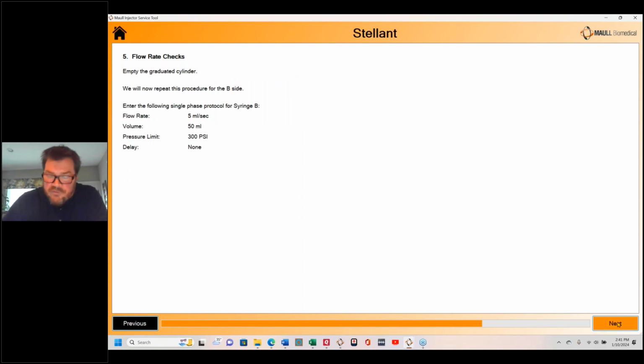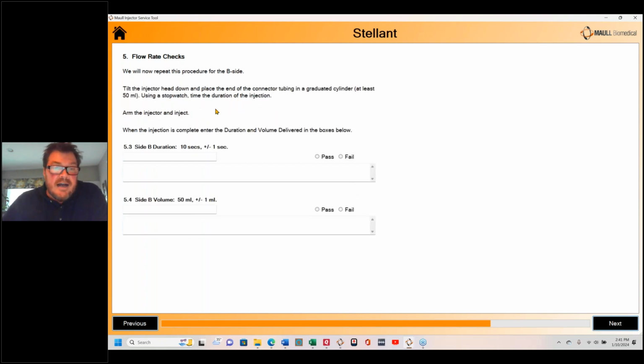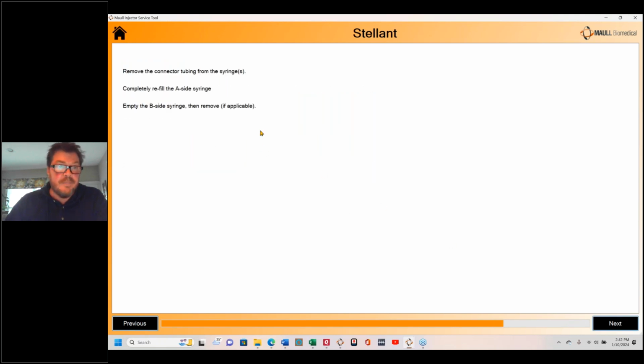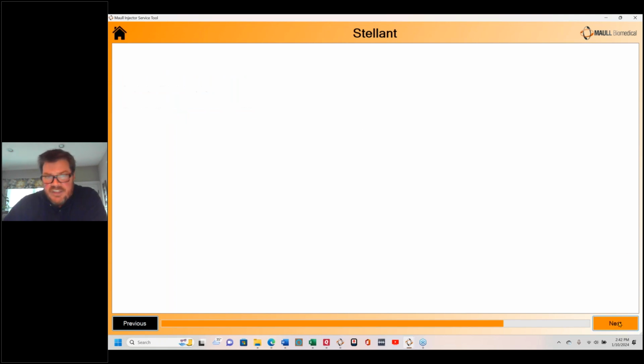And then we don't go through all the videos again. You just did it on the A side, so you'll know how to do it for the B side. And then this is the documentation for the B side results. 50 milliliters, 10 seconds, pass, and next. And then it's telling you to remove the connector tubing. So we're going to take the tube off the syringes. We're going to completely refill the A side syringe, and we're going to empty out the B syringe and then remove it for the things we're doing next.